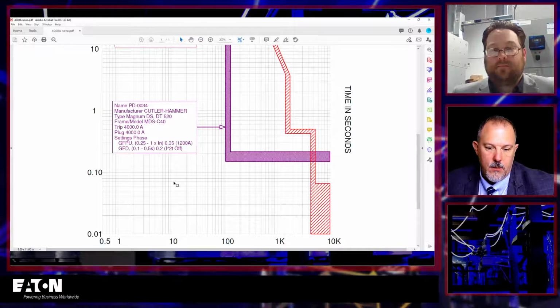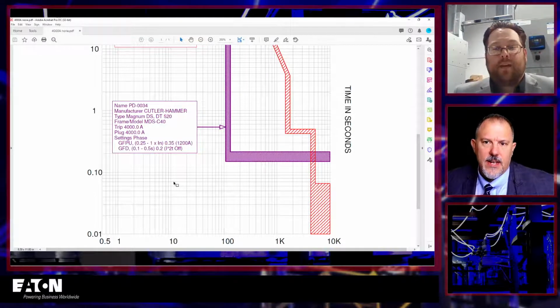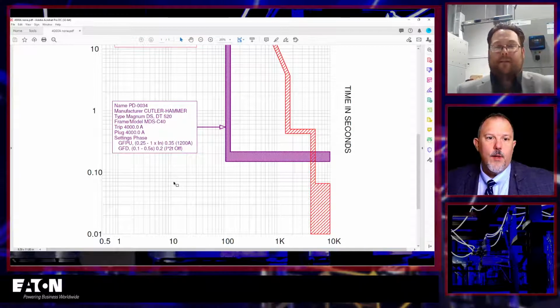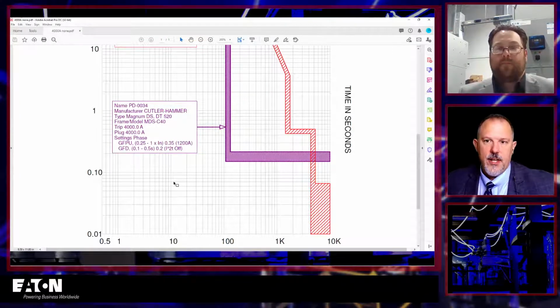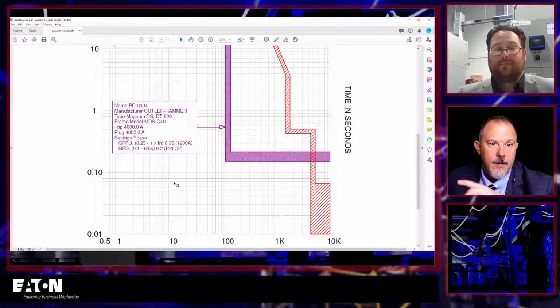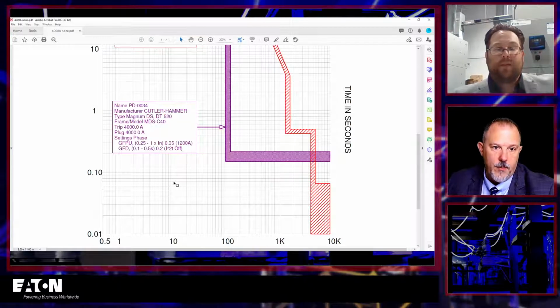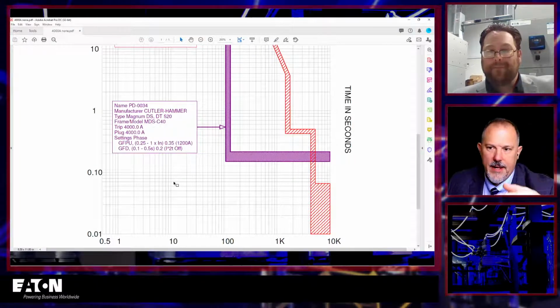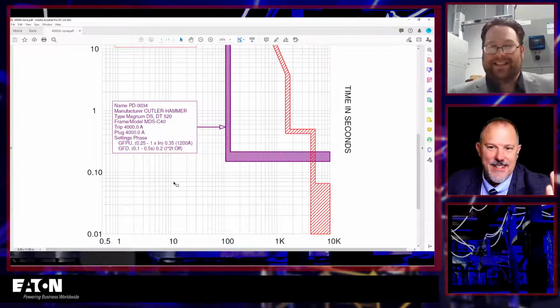mathematical law. It's like a rule; you can't violate it, like Ohm's law. They will all add up to 0, and we leverage that for the ground fault. To your point, what I'm showing here is a 4,000 amp circuit breaker with ground fault protection of equipment, and the GFPE is set at 1,200 amps. So that's a 4,000 amp circuit breaker, and GFPE is set at 1,200 amps. And Kirchhoff's laws, see that? He's the man. Ryan's got it. Ryan Jackson's in the house.